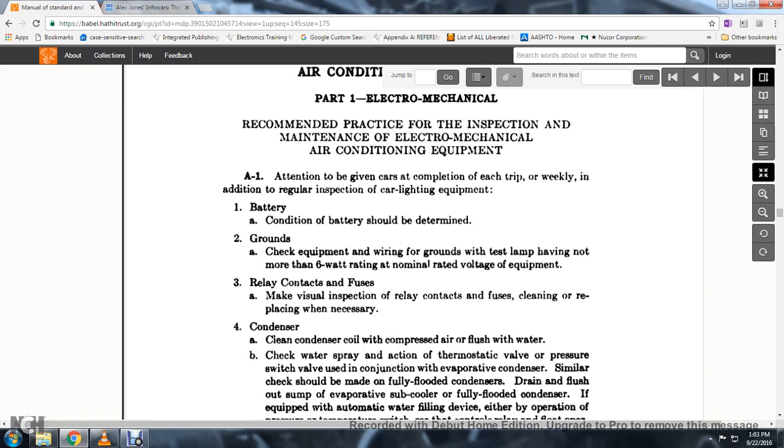4. Condenser cleaning: clean condenser coil with compressed air or flush with water. Check water spray action with the thermostatic valve and the pressure switch valve used in conjunction with the evaporative condenser.